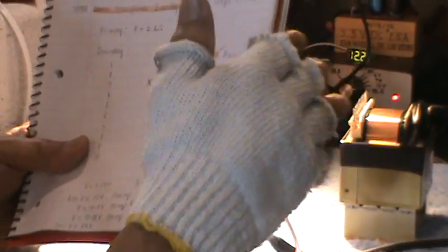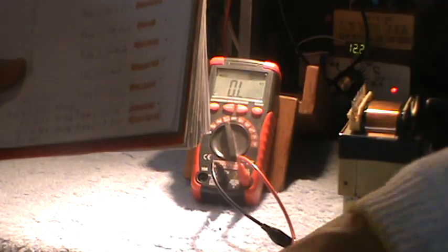I started with terminals 3 and 8, it's 15.6 ohms. So I am taking the resistances with every possible combination. So R38 is 15.6 ohms. 3 and 9 is 15.1. There is a value. So meaning to say, if we energize the primary, we could measure a voltage on those terminals because it has a resistance reading.